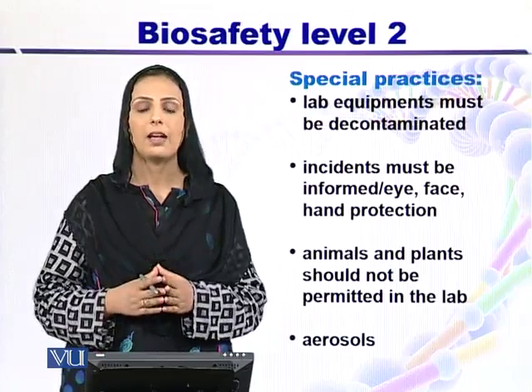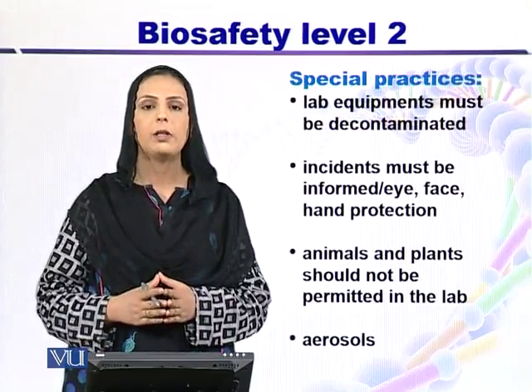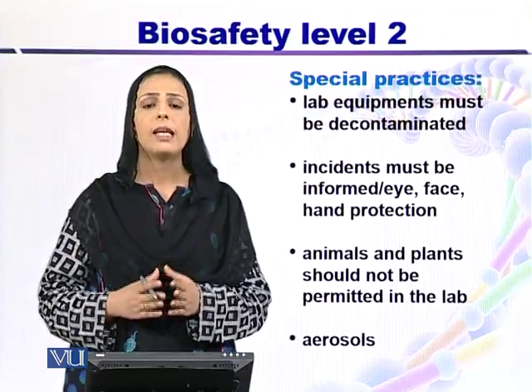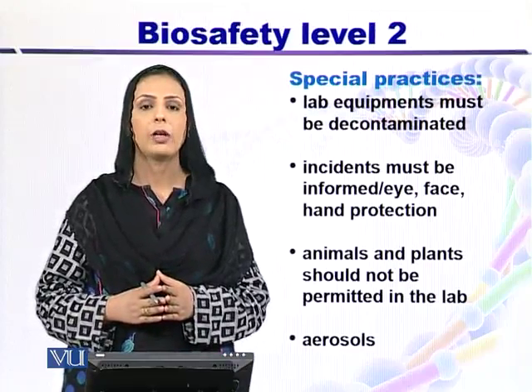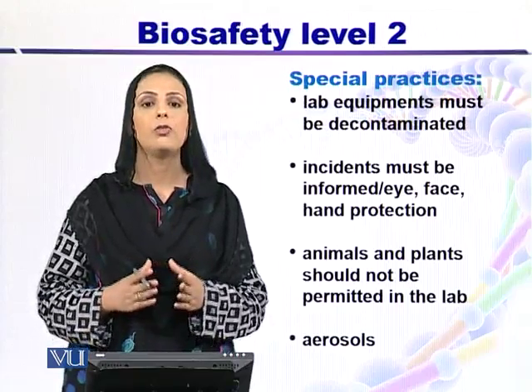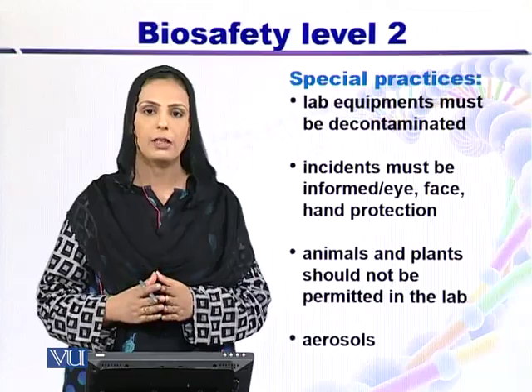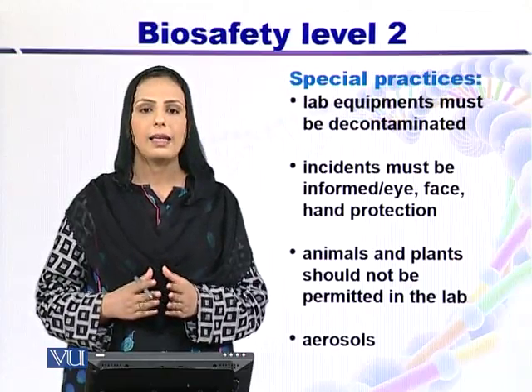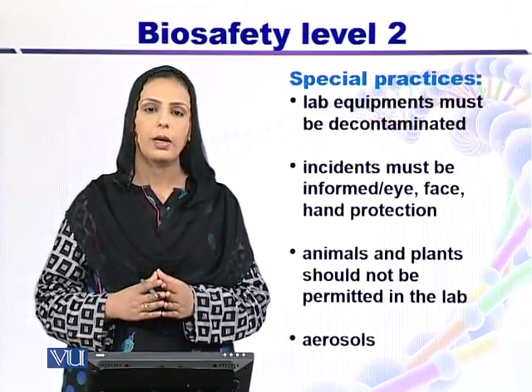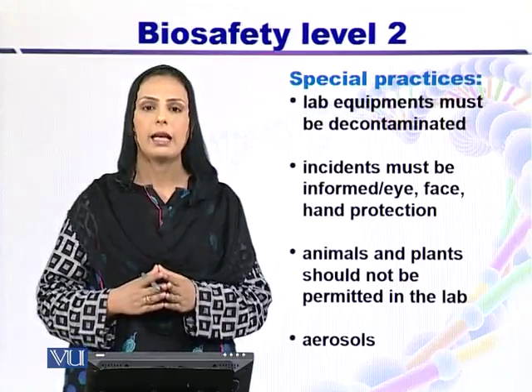Lab equipment must be decontaminated not only after performing a procedure, but also when equipment is removed from the lab for repair or maintenance, so that people outside the lab remain safe. If any incident such as a biological spill occurs, it must be reported to the biosafety officer so improvements can be made. Simple eye protective wear, face mask, face shield, and gloves are required for standard microbiological practices at biosafety level 2.